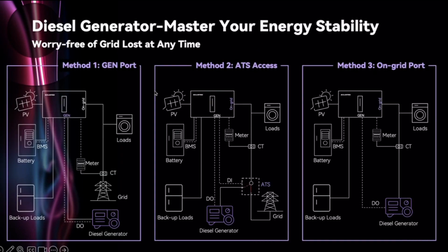And now let's take a closer look at how this inverter supports our system in real applications. As we have mentioned earlier, our inverter can be connected with a diesel generator, providing extra power and stability whenever the grid is unstable or unavailable. So for the single inverter system, there are three ways to connect with a diesel generator. The first method is through the GEN port at the bottom of the inverter. So here, the inverter can directly control the generator via its dry port for the start and stop signals.